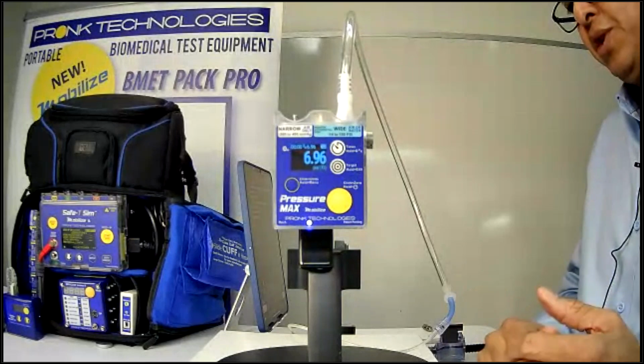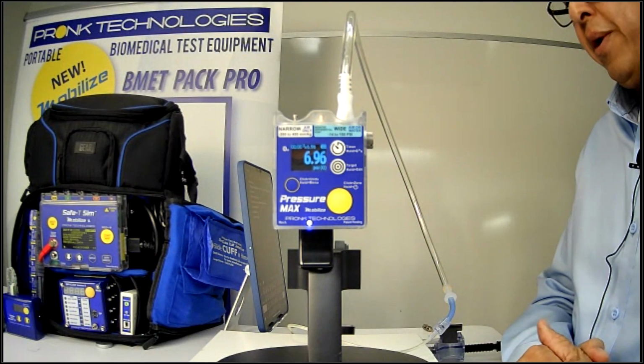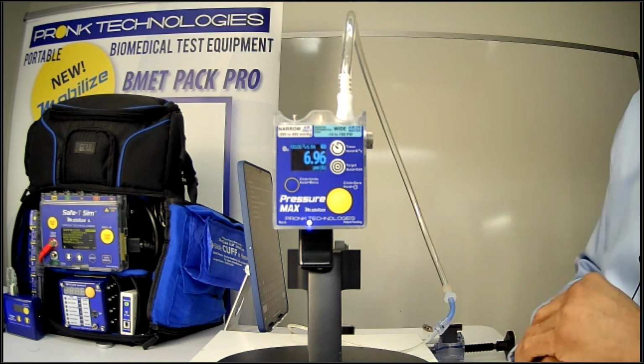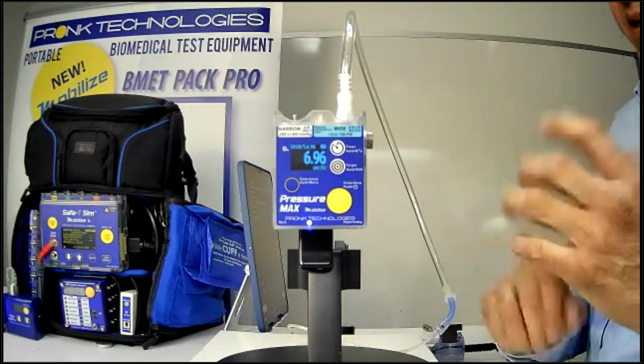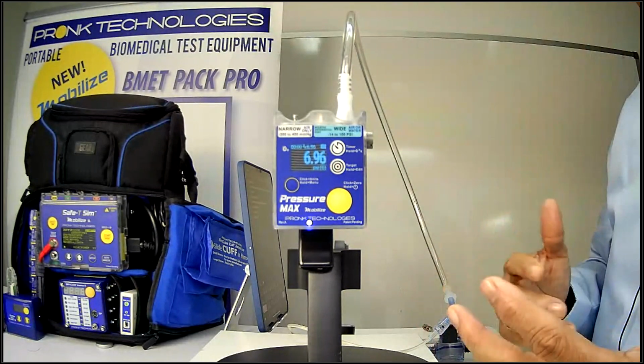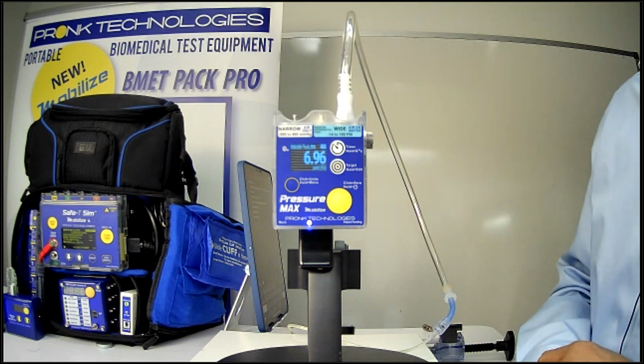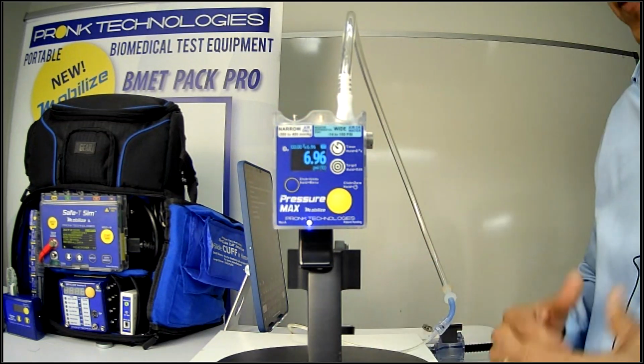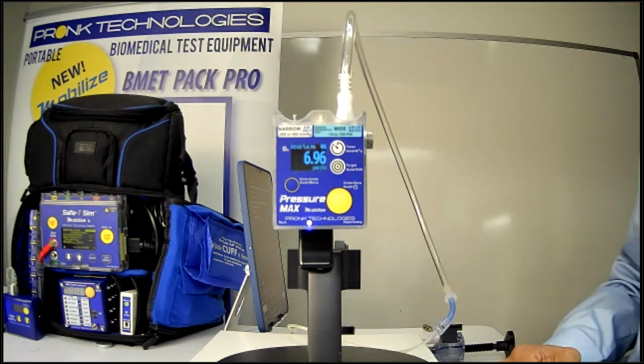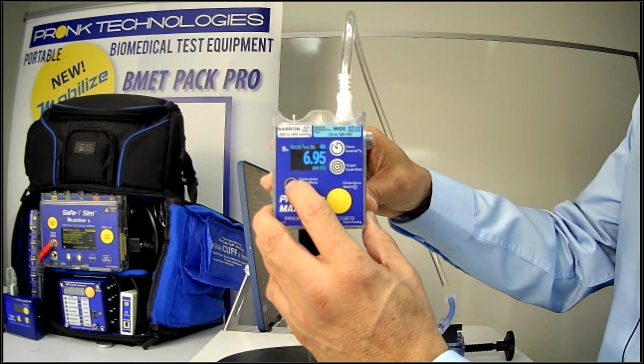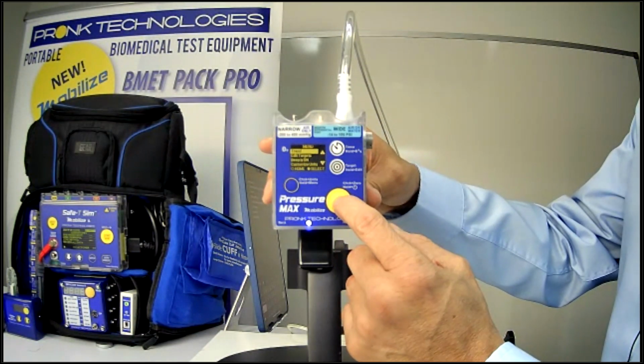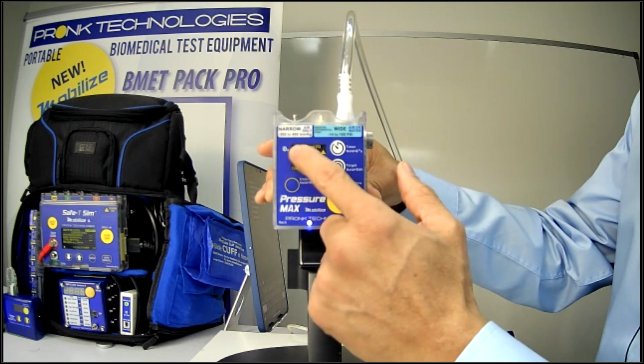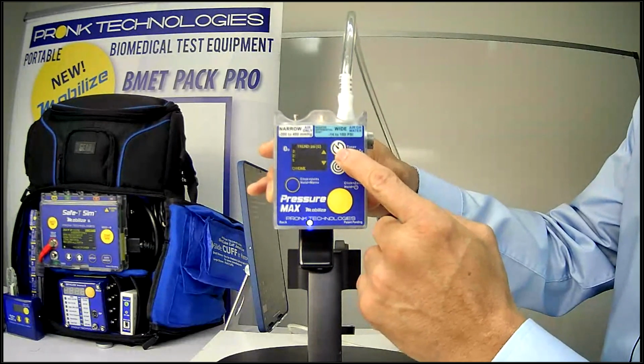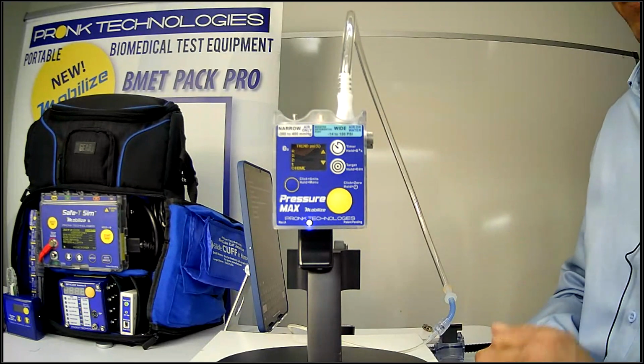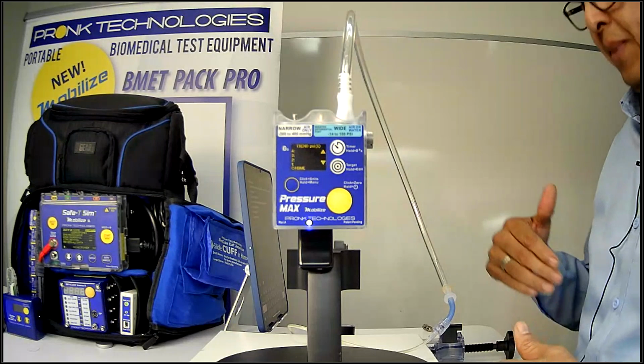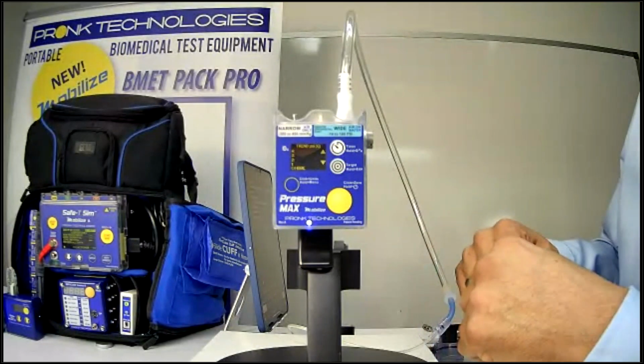So it's a simple feature, but it was a suggestion from one of our customers that we're partnering with to do the design of the product. Like, can you set it up so that I can edit my units of measure and I don't have to keep going and selecting them? So you can even just have 1 unit of measure. You could have 2, anything from 11 on down. Just select your units of measure, and then you're just toggling between those 2 values. So really try to customize and give the user flexibility to be able to make those customizations they want on the unit. So we mentioned that you can edit the targets here. There's a trend function here, which will get enabled as soon as I start and go into the trend function here. So as time goes on, you'll see that the pressure measurements will increment and be displayed here in 1-minute intervals, so that you can trend maybe changes in pressure for the last 15 minutes to be able to see those values. So we'll come back to that in a moment.